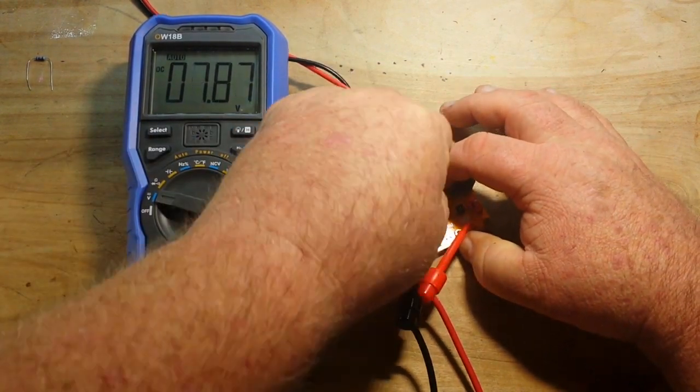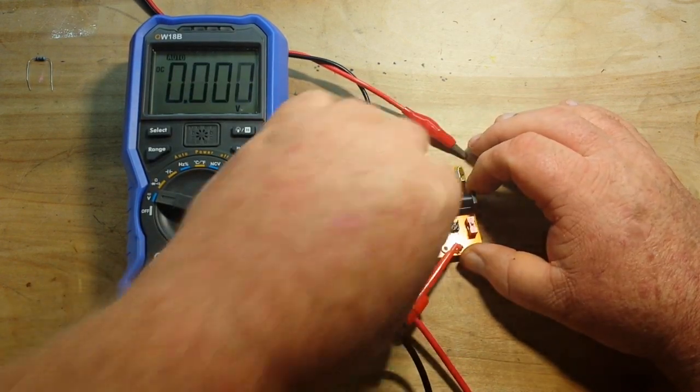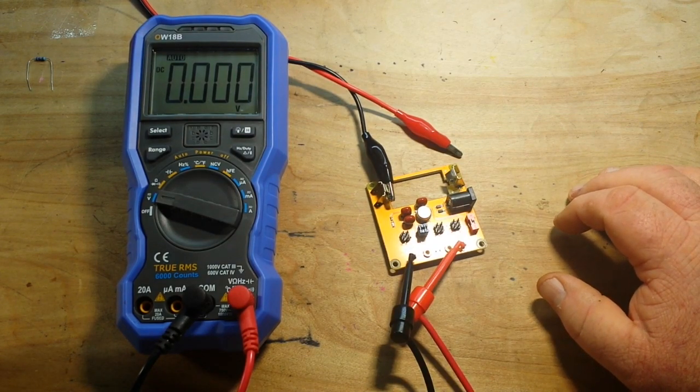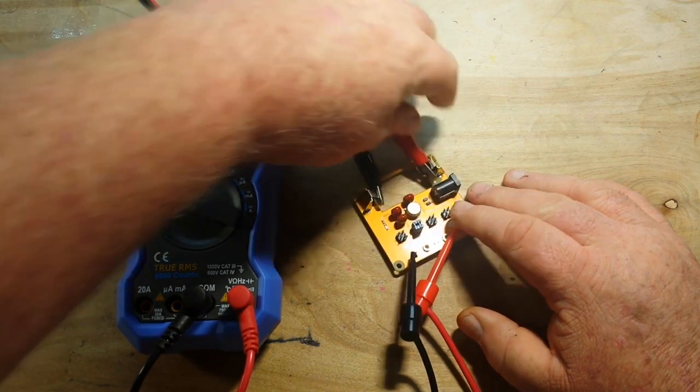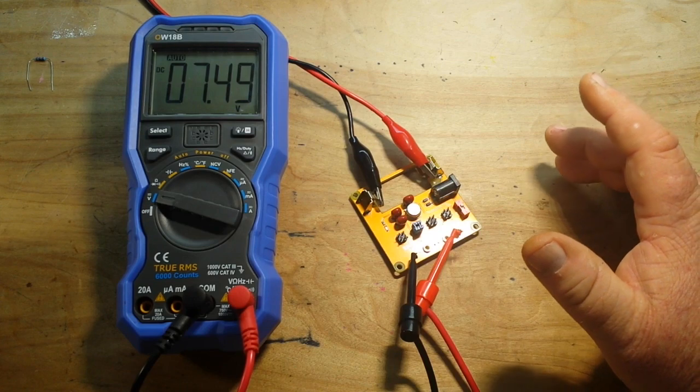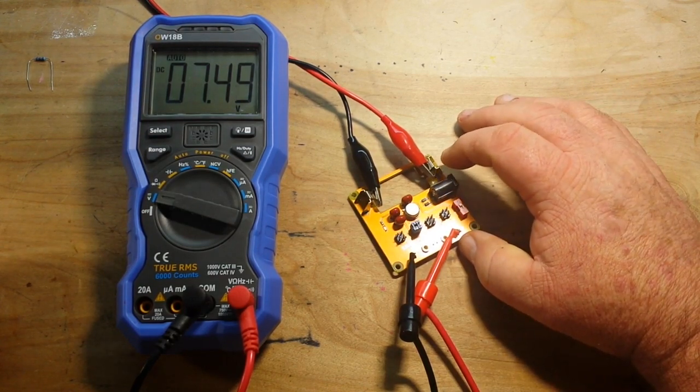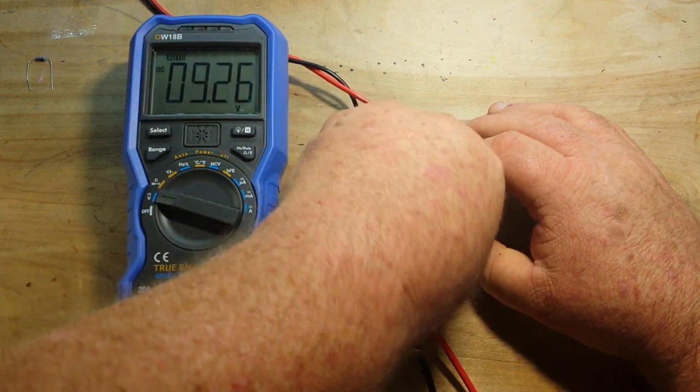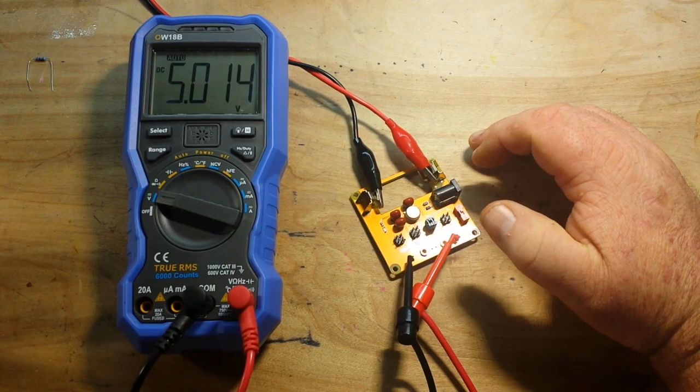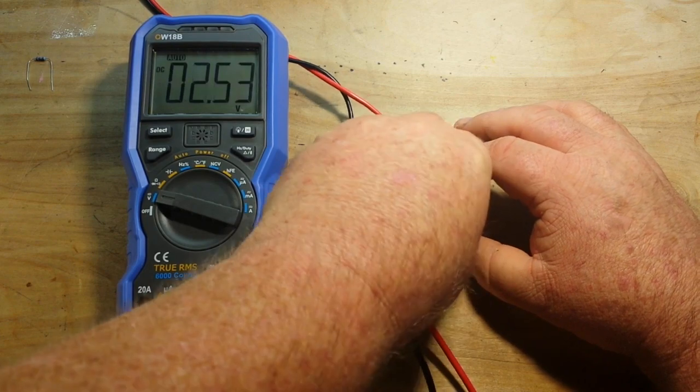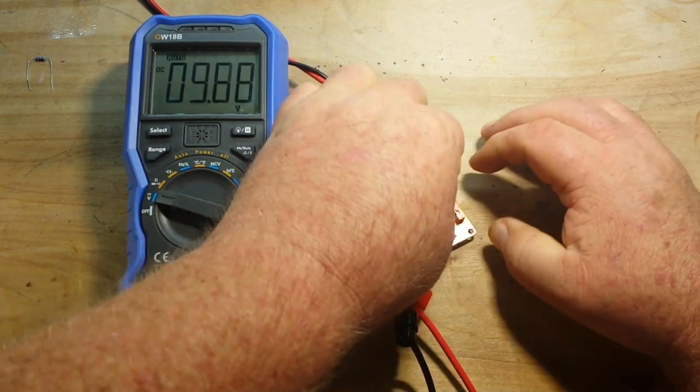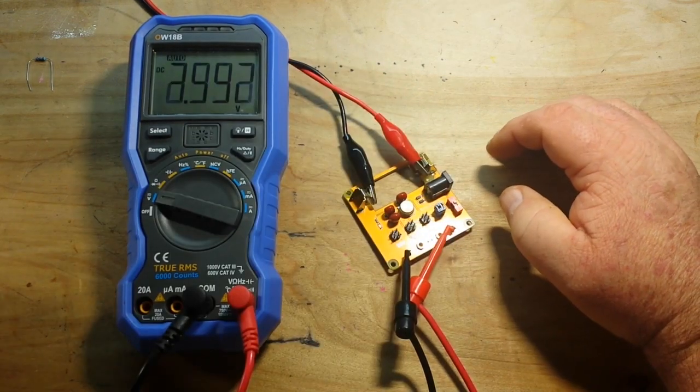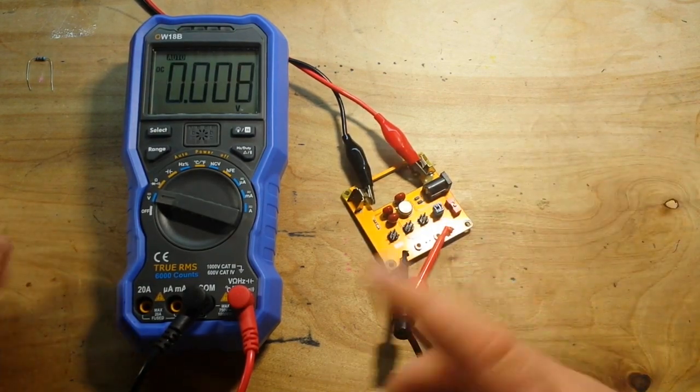It might be that little fluctuation off that battery. But you can see we pretty well stabilized at 10 volts there. No problem. Let's go down to 7.5. Lost my power lead. 7.49, definitely close enough for anything that we need here. 5 volt. 5.014. Excellent. And our final check, if I can get these little jumpers on, it's 2.5 volts. 2.506. Again, excellent. No worries there.